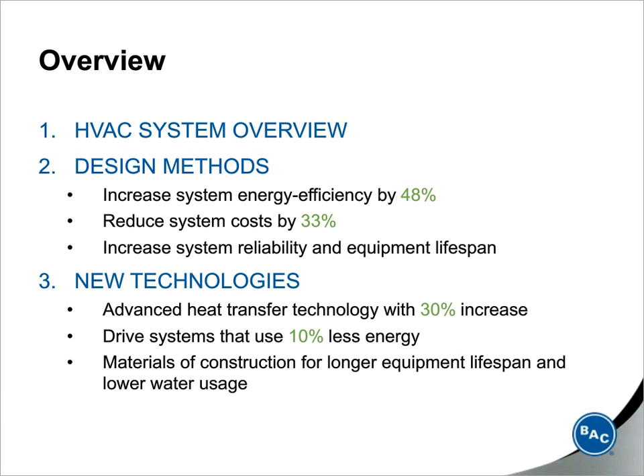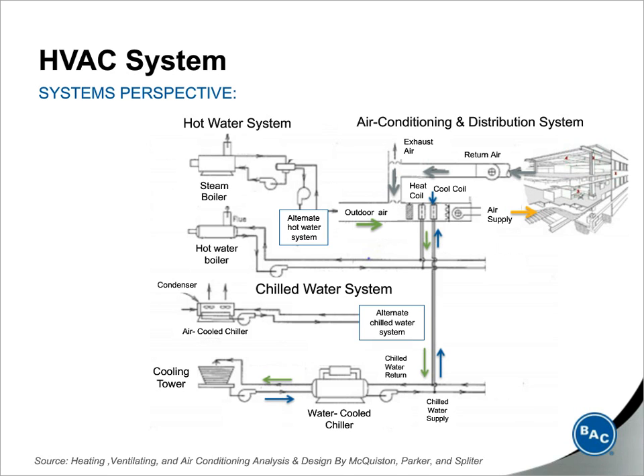So with that, let's start with an overview of the HVAC system. Now, this schematic that's shown on the screen represents a very typical building with a chilled water system. This system includes a chiller, but the same general layout is going to exist for a heat pump system as well, or other systems with those components replacing the chiller. And the purpose of the chilled water system is really strictly to remove heat from the building and cool the required interior space. From a systems perspective, there are three main subsystems that complete the total HVAC system.